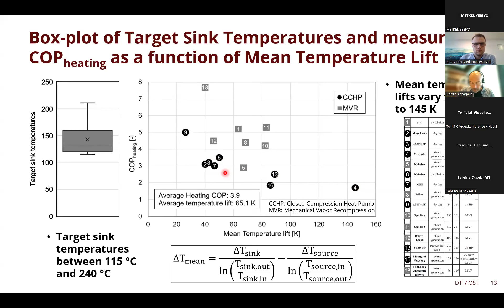And as expected for the closed cycle compression heat pumps, the COP decreases with higher lift, but they are at a relatively quite high level. Now we can overlap the MVR cases, and they achieve higher efficiency than the closed cycle heat pumps because they work in open mode of operation. Number 4, for example, here is a Stirling heat pump, which achieves the highest temperature lift, followed by the MVR applications. So at the lower temperature lifts, closed cycle heat pumps are the predominant technology. And for steam generation, we have different combinations. We'll see this later.